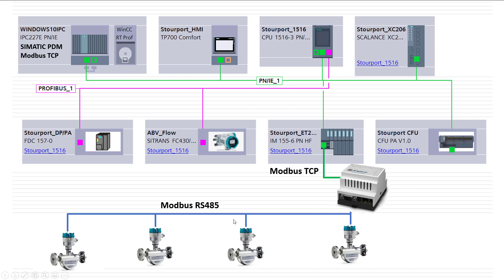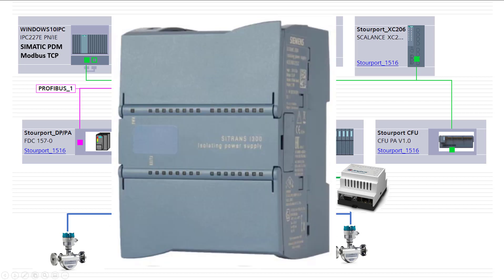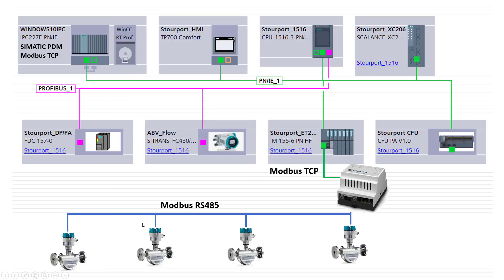If I want to have hazardous area, well the beauty of the 410 and the 310 complete system Coriolis meter—it's certified to zone 2 anyway, so you don't need any barriers. If you want to put that into a zone 1, then you can add a barrier package to this network and it will support up to I think 8 devices. If you want to, you can put one on each spur and then that would protect the power supply. So it's still a low-cost solution.